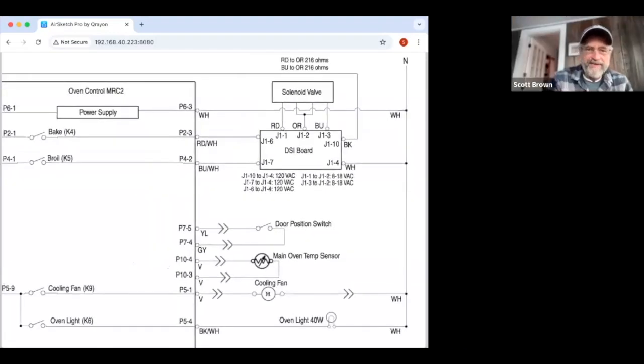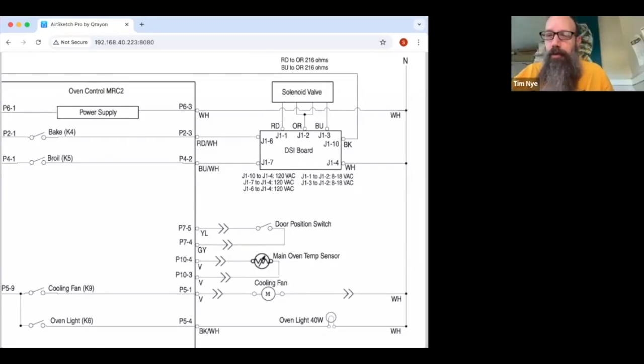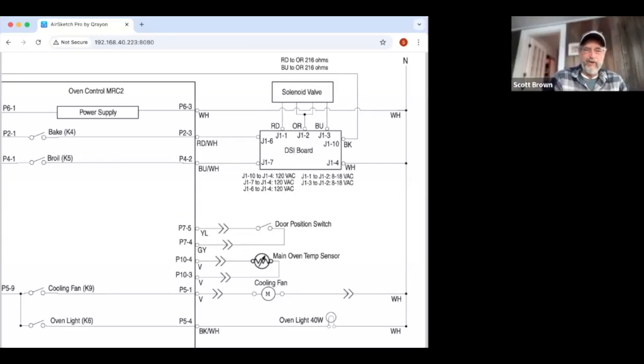But anybody know what that spark voltage typically is in the range of? What kind of voltage is at that spark electrode? You tell us every few months and we always forget. It's like between 12 and 15,000 volts.